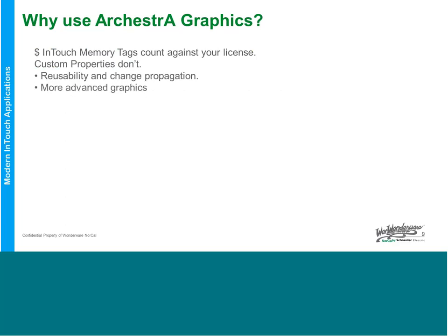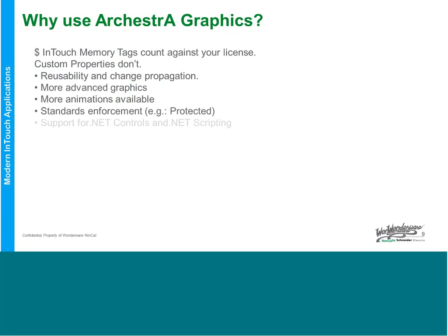For one, InTouch memory tags count against your license, but custom properties inside of ArchestrA Graphics don't. So you can actually reduce your tag count and reduce your licensing cost. ArchestrA Graphics allow you to reuse graphics and promote change propagation. I'll do a demo for that and show you what that looks like. They're more advanced graphics, so there's more animations available. It's a whole new symbol editor that allows you to really get creative in how you build graphics. You can embed .NET controls and .NET scripting inside of graphics for more advanced programmers.